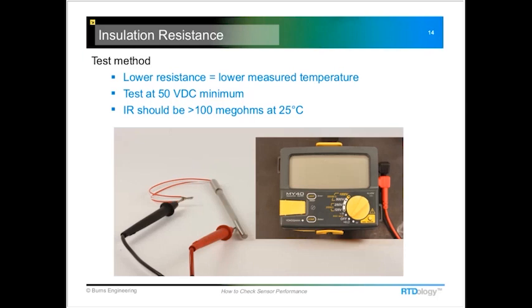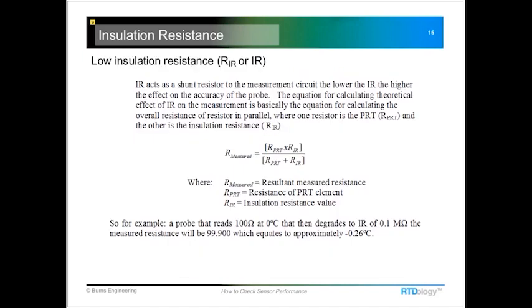For most industrial applications, if the insulation resistance is down below 10 megohms at the temperature that the probe is running at, there should be cause for concern, because it would indicate that something has gotten inside the probe, most likely moisture, causing a low insulation resistance. You really don't start to see any significant accuracy effects until you get down below roughly 1 megohm of insulation resistance. And we can run through a little calculation here to see what that is.